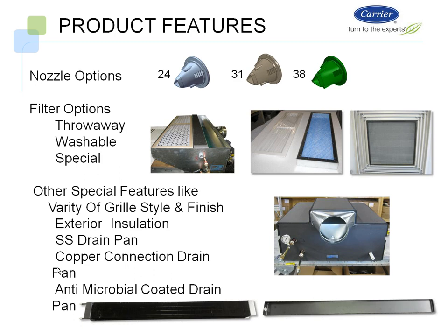Also, we offer different nozzle options, and the reason is, let's say the space changes after it's been designed. A year later, maybe you need more capacity or more airflow out of that unit. These nozzles are plenum rated, fire rated, etc. But with simple needle nose pliers, you can pull these out and replace them with a larger nozzle. The triangular nozzle is actually there to get a better sound level. With a rounder type nozzle, your sound levels get worse. So this design allows for better sound levels, and I can configure a box and get more capacity out of that box just by changing the nozzles.